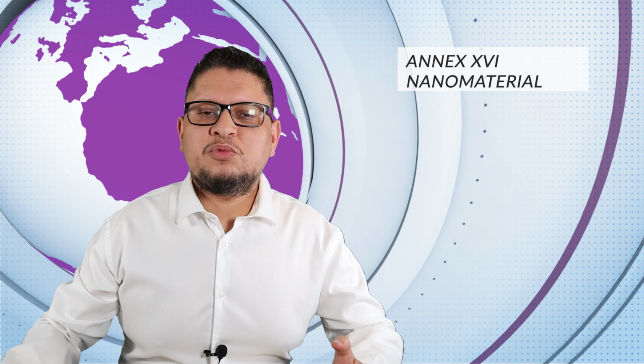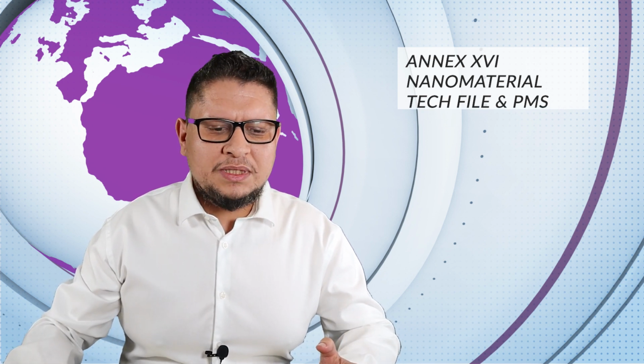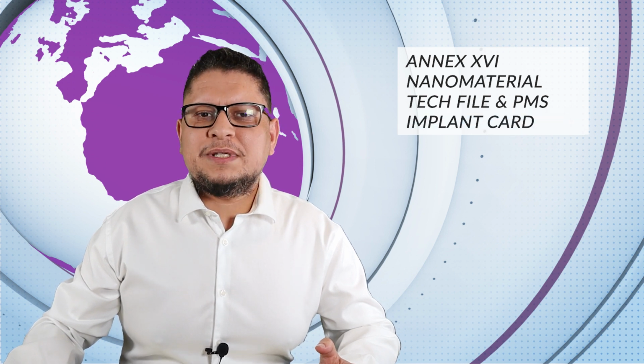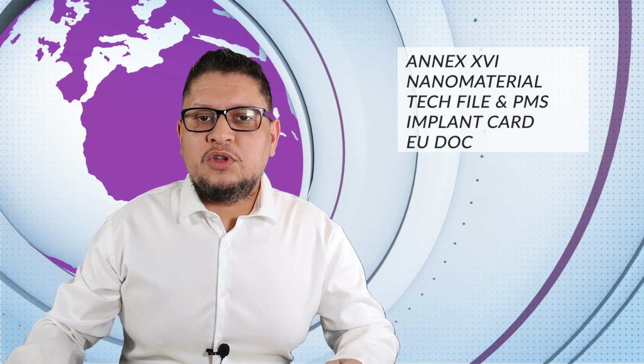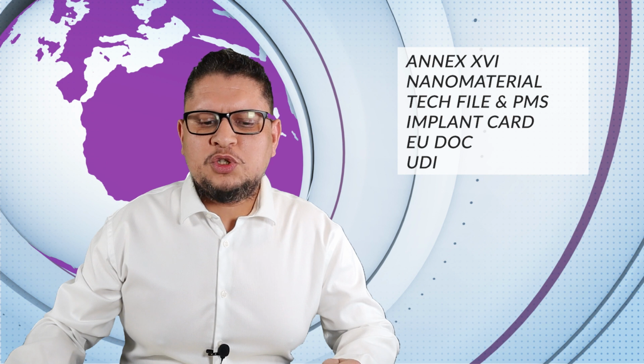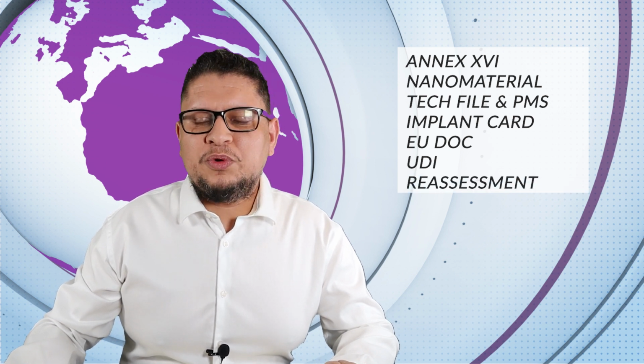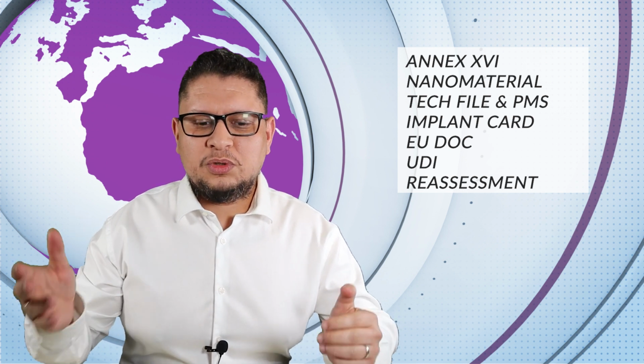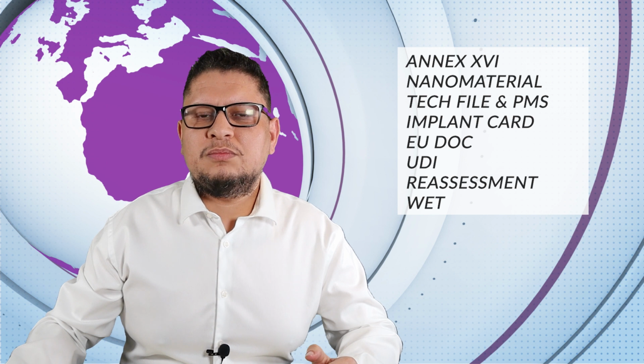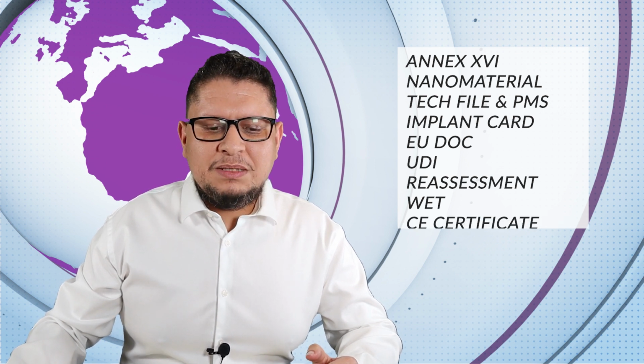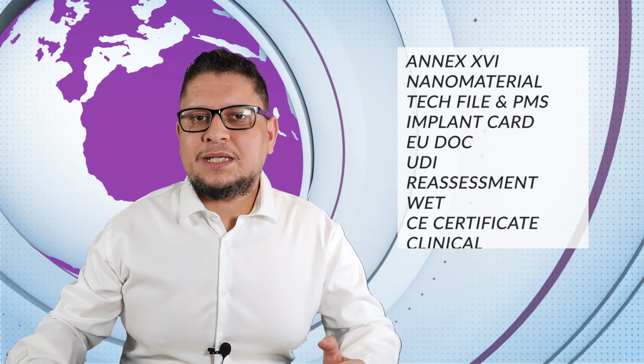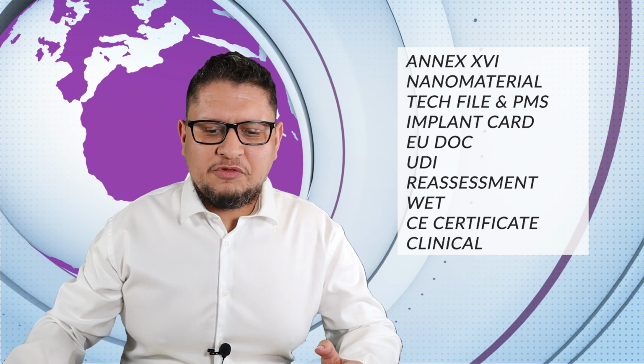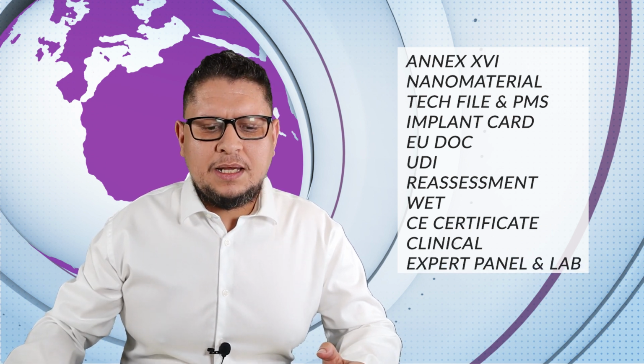Another thing is, for example, nanomaterials. We actually have a definition of nanomaterials inside the EU MDR. Maybe they can also update that. The other updates can be the elements on the technical files or the post-marketing surveillance, so Annex 2 and Annex 3 of the EU MDR. The exemptions from the requirements in terms of the implant card, the minimum content of the EU Declaration of Conformity. You have also information to be submitted for UDI, the frequency to complete the reassessment of notified bodies, so if they can reduce or increase that also. The exemptions related to some well-established technologies. The minimum content of the CE certificate for notified bodies, the documents regarding the clinical investigation and interventional clinical performance studies, and the tasks of the expert panels and expert labs.